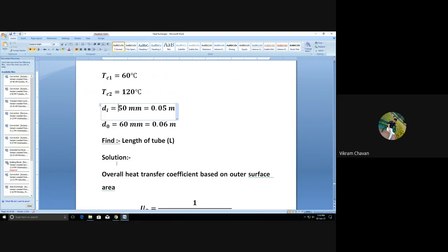Then in which formula of a heat exchanger is the area included? We know that Q is equal to U multiplied by A multiplied by theta suffix M. That is the overall heat transfer coefficient multiplied by the equivalent area multiplied by the LMTD, that is, the logarithmic mean temperature difference. So in that formula the area is included.